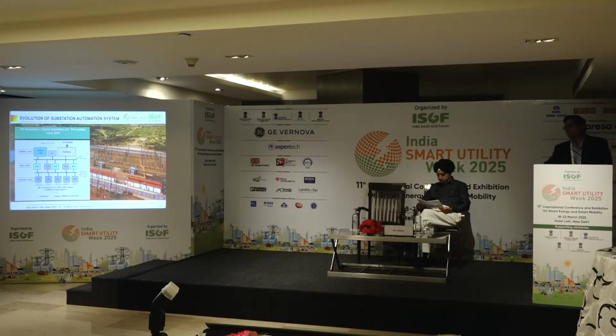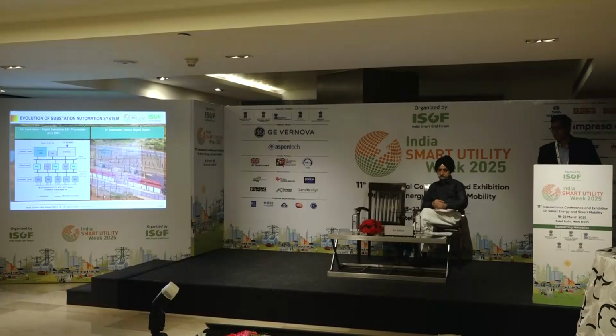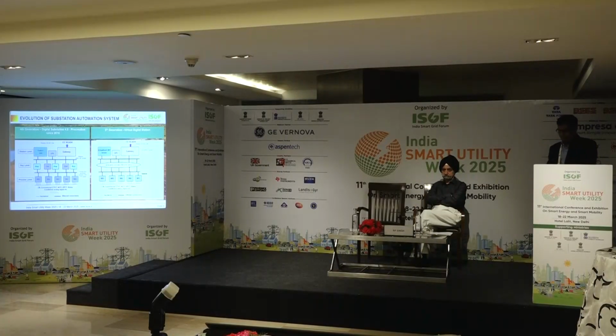For time synchronization, it is also very critical. In the station bus, we are using SNTP, which can give you millisecond range accuracy, whereas in this case, PTP will give microsecond accuracy, which will fulfill our requirement. Now here you can see that at the bay level, we are using a huge number of protection and control devices. Definitely it will come to mind that this is one of the things contributing a big cost to digital substation 4.0. Not only that, the Ethernet switches we are using are compliant to IEC 61850 as well as PTP compliant, which makes them very expensive items.